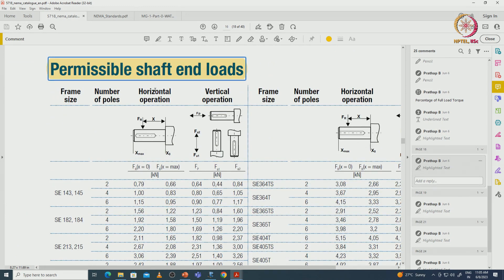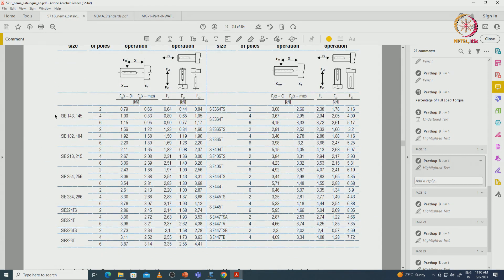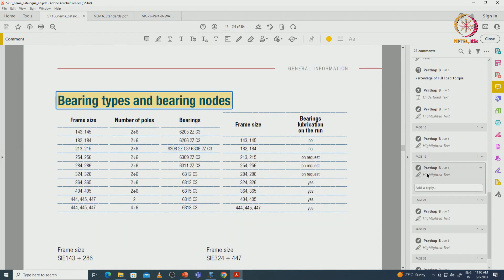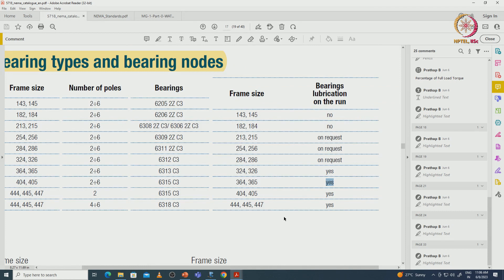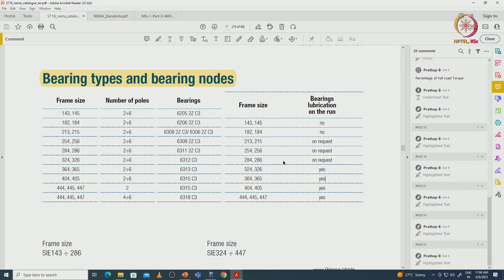Permissible shaft and end loads for different sizes can be selected based on torques, speeds, and bearing types. Standards also specify bearing notation, frame size, and bearing lubrication requirements. For example, for frame sizes 404 and 405 with certain pole counts and bearing structures, lubrication is required, while for other smaller frame sizes lubrication may not be needed.